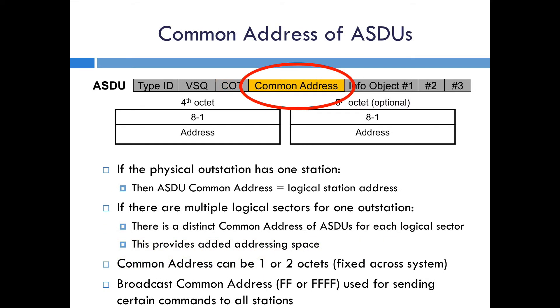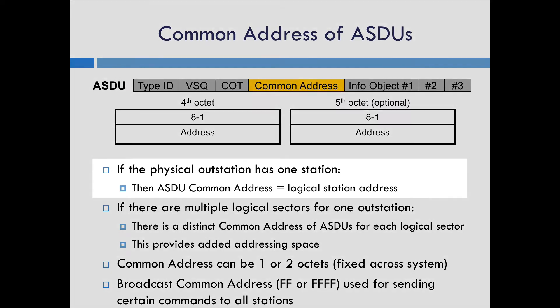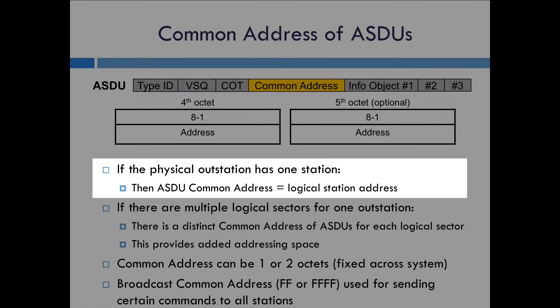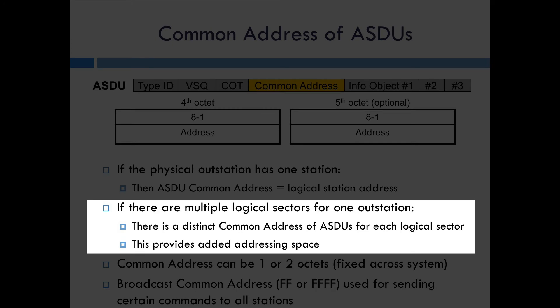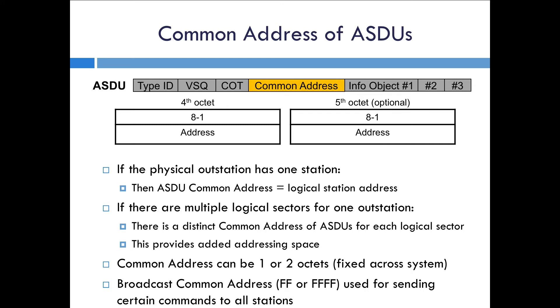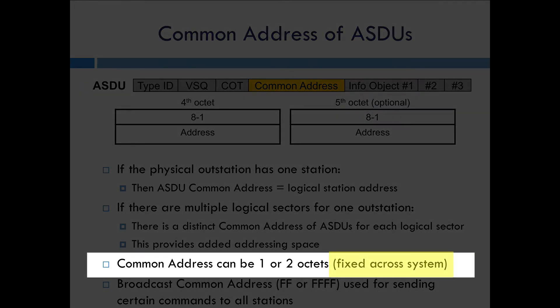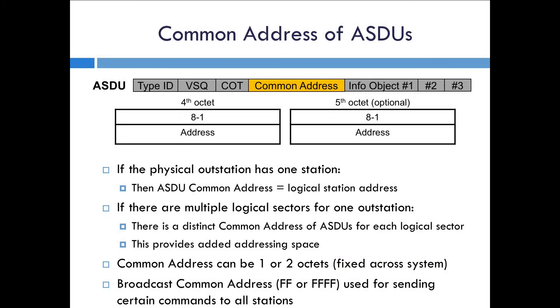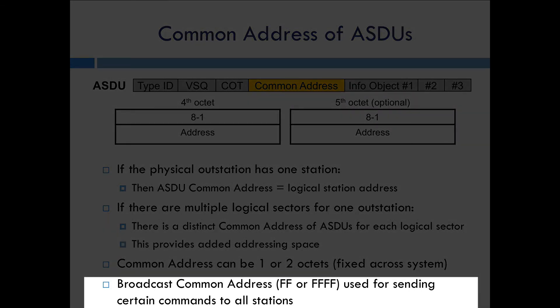The last part of the ASDU header is the common address. Each physical outstation can have multiple sectors, so there are several different ways to handle addressing. If you have just one station in one sector, the ASDU common address really is the station's address. If you want multiple logical sectors for one outstation, you can have a common address for each sector, expanding your addressing space and allowing you to segment different objects into different sectors. The common address can be one or two octets, but that's fixed across the entire system. There's also a concept of a broadcast address — set to FF for one-octet addressing or FFFF for two-octet addressing — which all outstations will see and process.